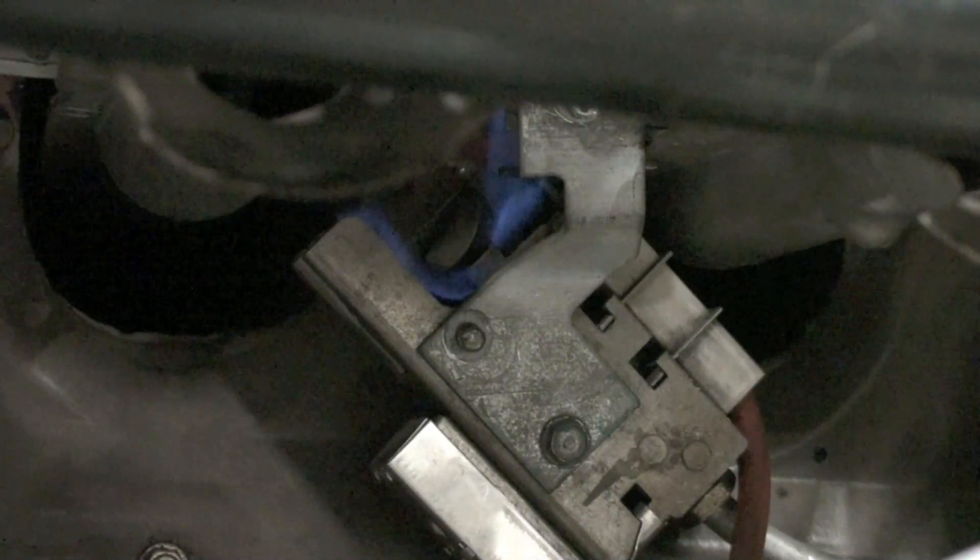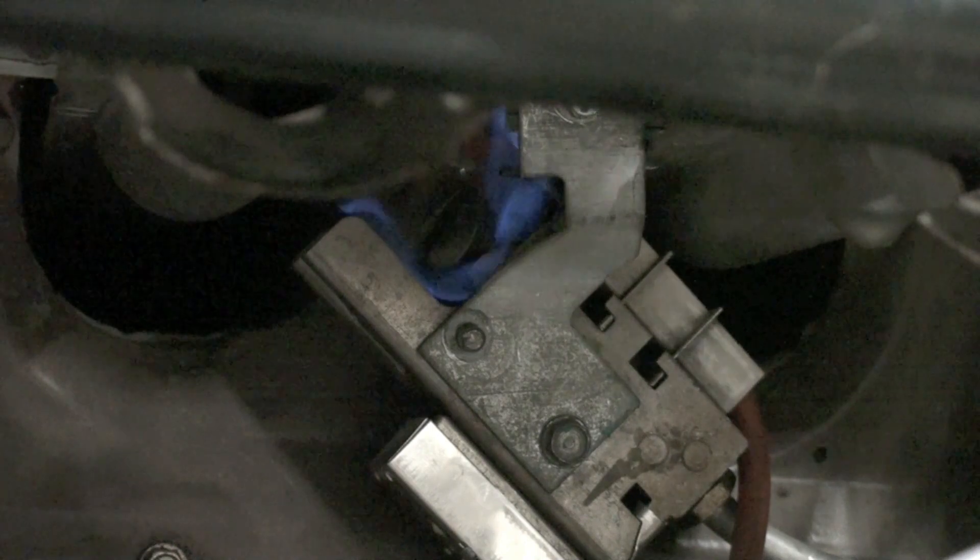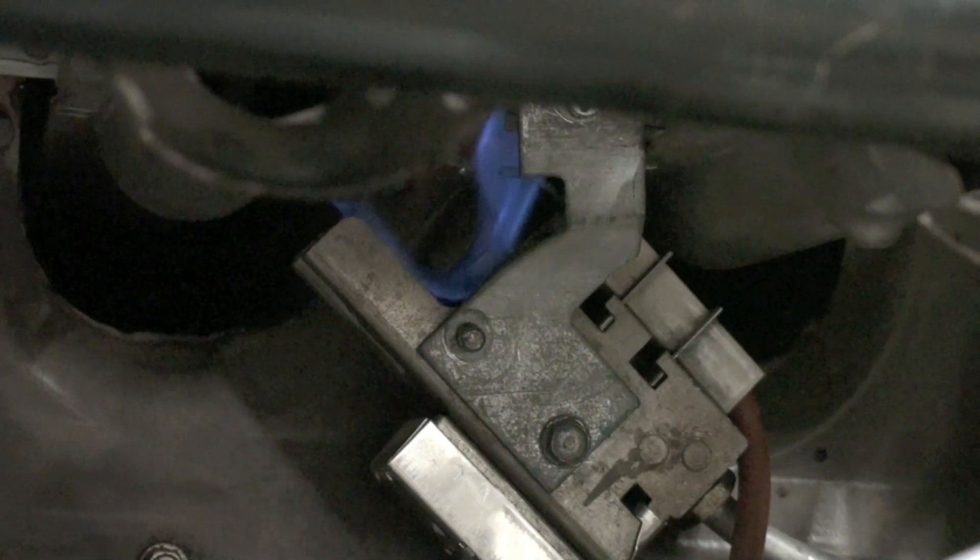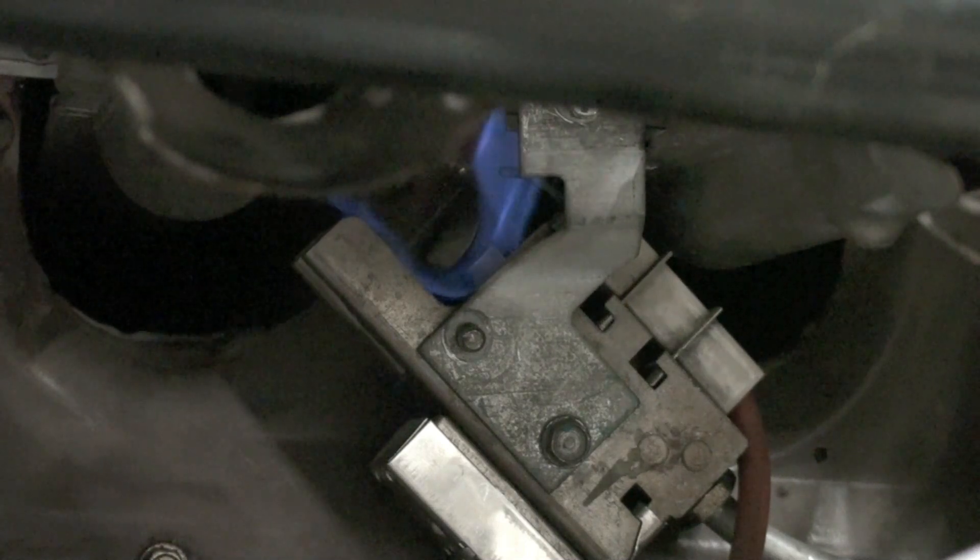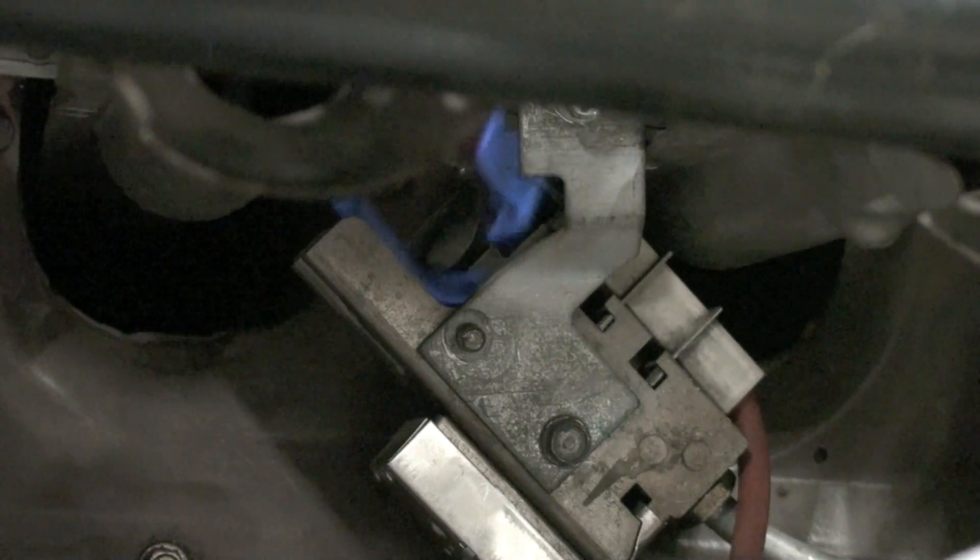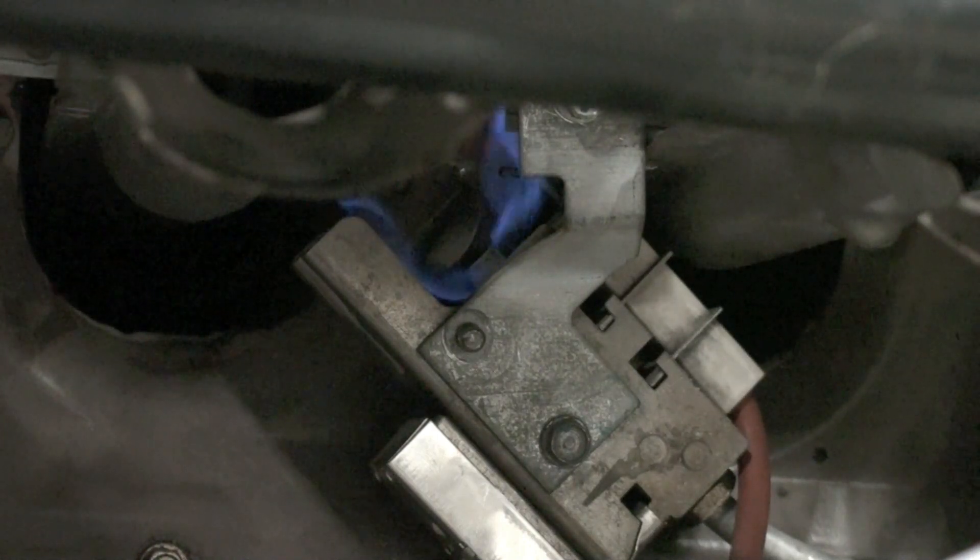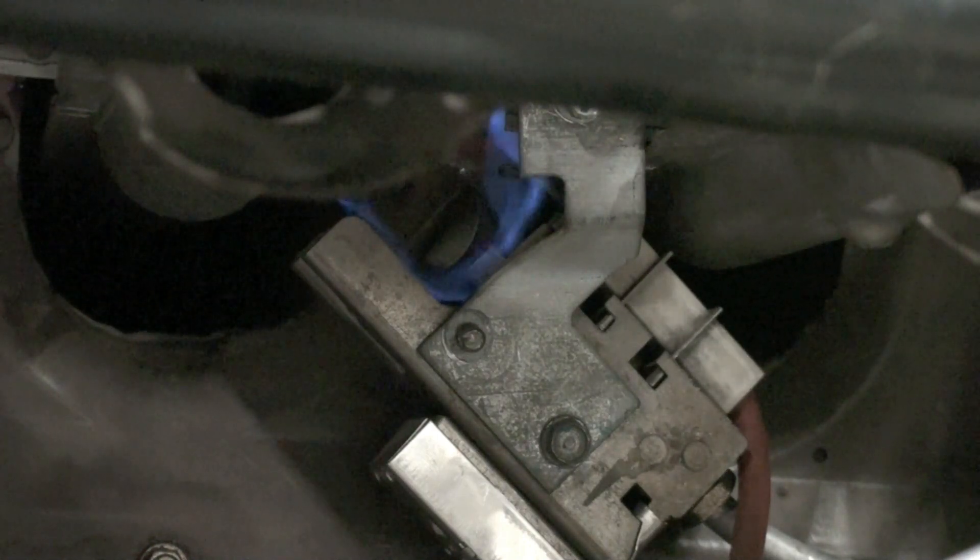Okay, there's our spark. Our pilot is lit now. The flame on the left is warming the bi-metal to make the switch. The flame on the right will actually light the burner.